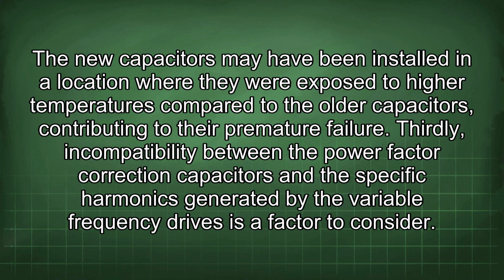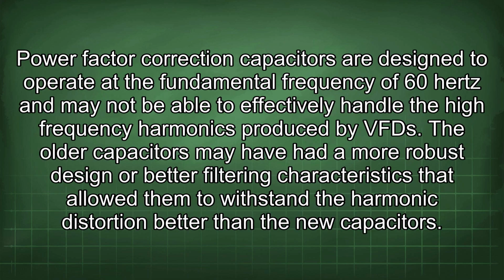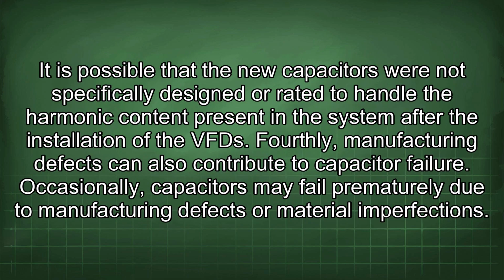Thirdly, incompatibility between the power factor correction capacitors and the specific harmonics generated by the variable frequency drives is a factor to consider. Power factor correction capacitors are designed to operate at the fundamental frequency of 60 Hz and may not be able to effectively handle the high frequency harmonics produced by the VFD. The older capacitors may have had a more robust design or better filtering characteristics that allowed them to withstand the harmonic distortion better than the new capacitors. It is possible that the new capacitors were not specifically designed or rated to handle the harmonic content present in the system after the installation of the VFD.